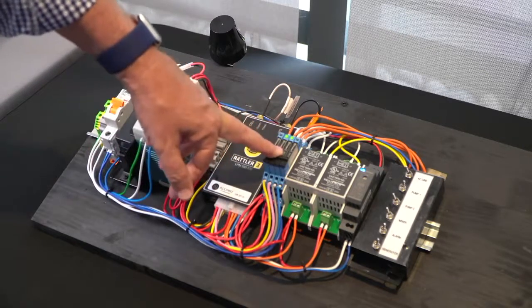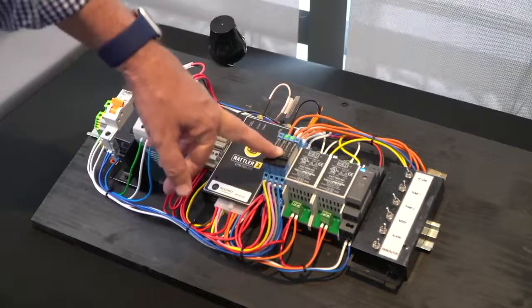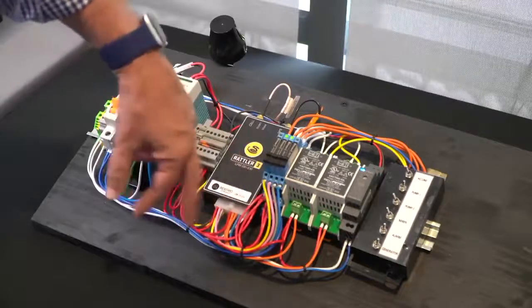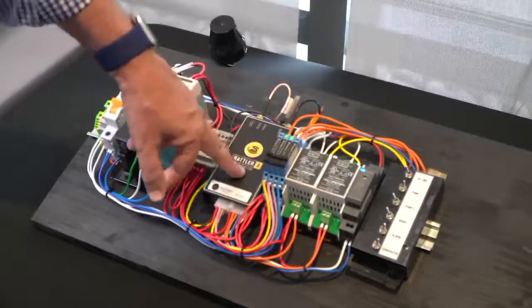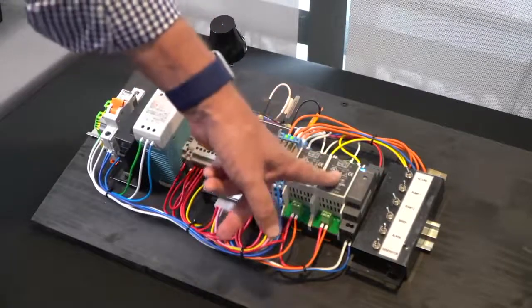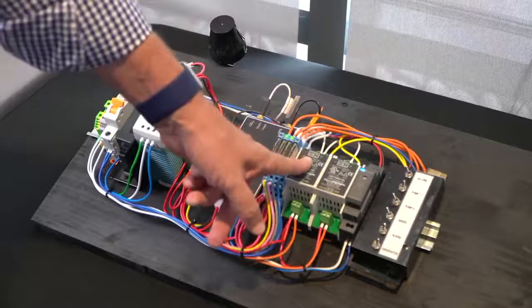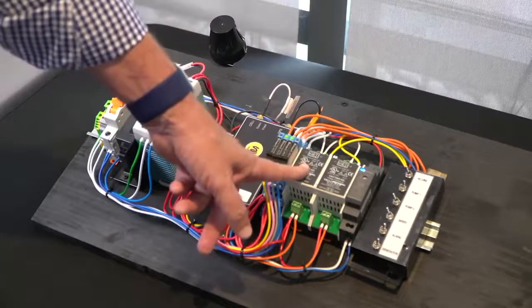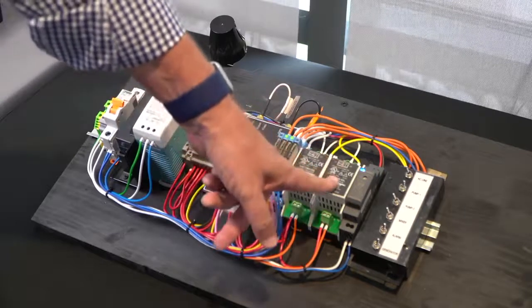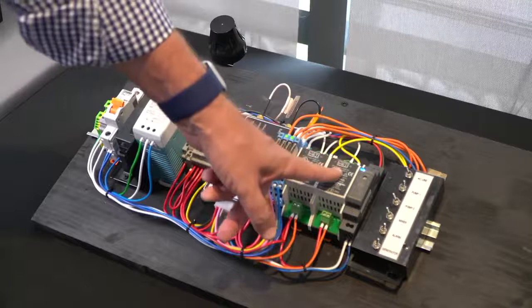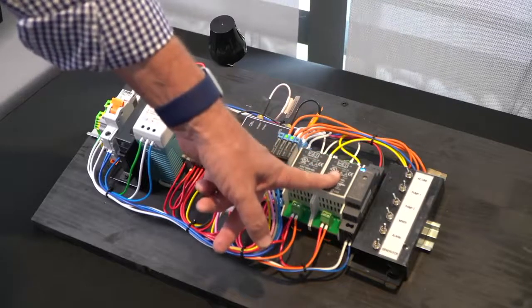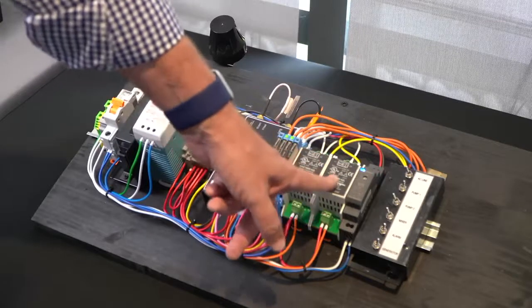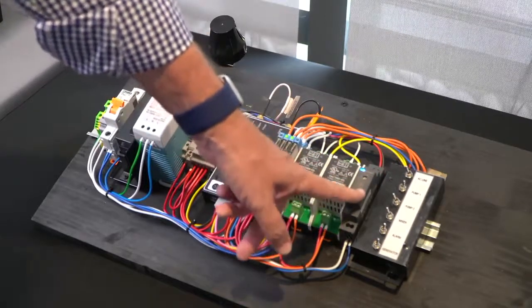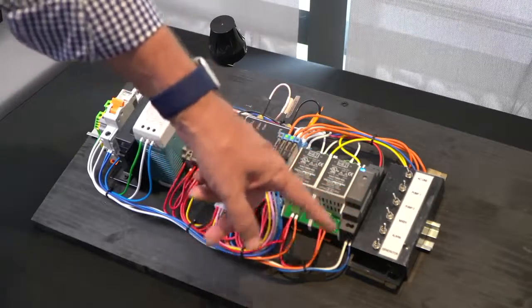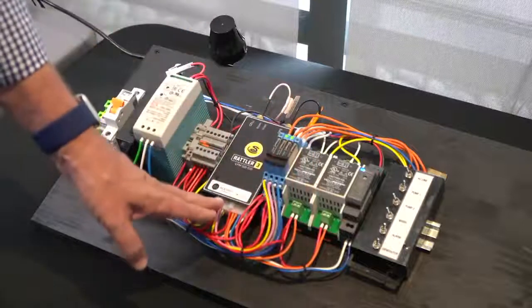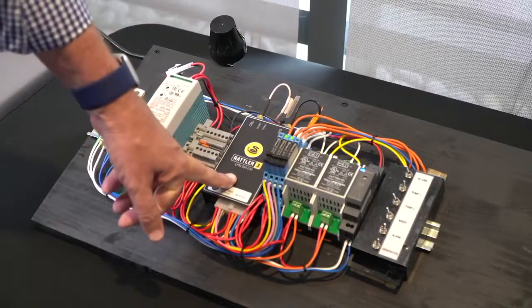Here are some conditioning relays, and what they do is they convert 240 volt or 480 volt or 110 volt into the 24 volt signals that the Rattler needs, 12 to 24 volt. Over here are two 4 to 20 milliamp power conditioning monitors. What they do is you want to know the quality of the AC that's coming in, and you want to know the quality of the generator power. Now this application has a standby generator, and that is why we have two of these, one for the AC power and one for the generator. This is a 24 volt power supply that provides an isolated loop power for the 4 to 20 milliamp inputs. And these all come through this wiring into the Rattler and are communicated to the cloud up into Glance.